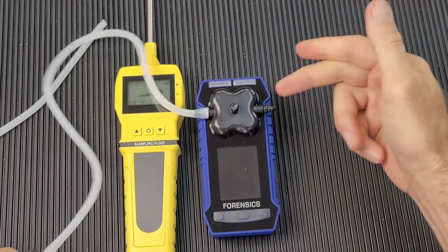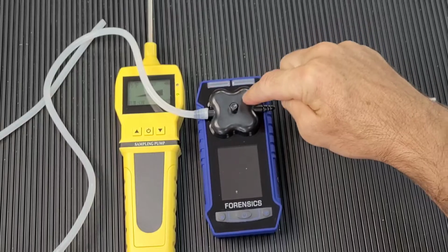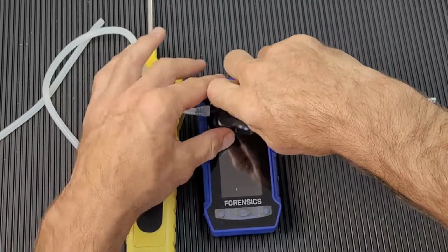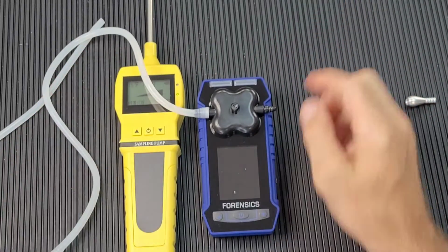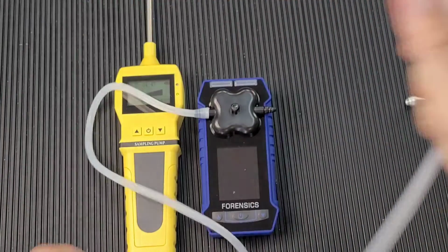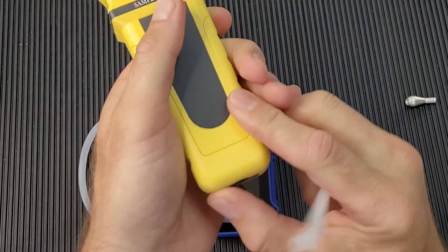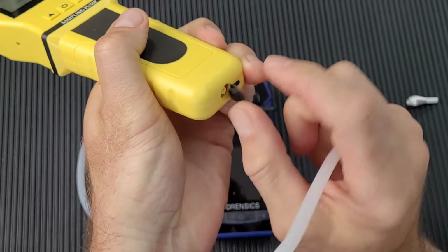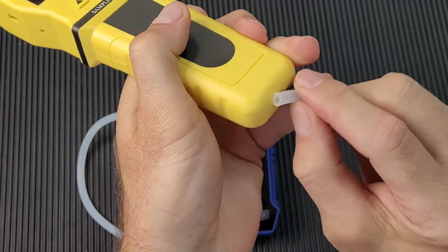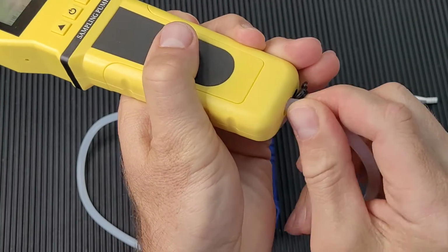Okay, folks? Now, you saw what happened here. The calibration cap is right here. You're going to pop it on with the nut. Make sure it's nice and tight, okay? Then the other end goes onto the pump at the bottom here. Okay, that's the outlet, folks. Air is coming out, it's getting drawn at the end, and it's coming out at the bottom. Put that on very nicely, nice and tight.